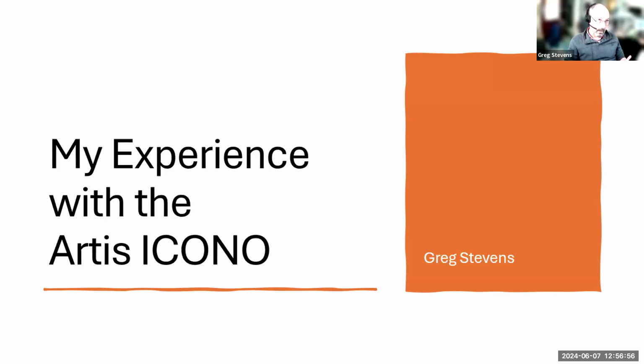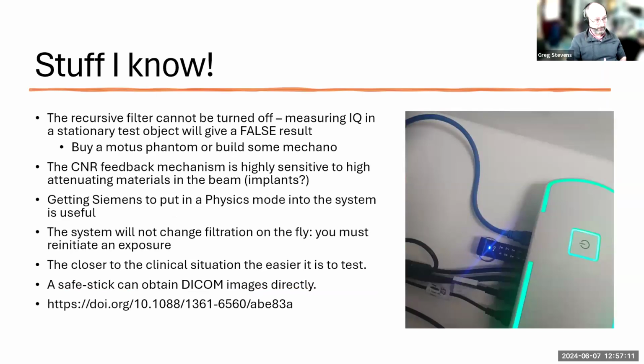For bariatric patients, they tend to be higher. But on average, the cumulative doses are lower. So, stuff that I do definitely know about: the recursive filter is on all the time. A recursive filter is something that just takes a proportion of the previous image and adds it to the new image. So your signal goes up, your noise goes down. This is absolutely fantastic if you've got stationary objects, because effectively you've got a lot of averaging, which is great, but it gives you a false result for your image quality. So just bear that in mind.